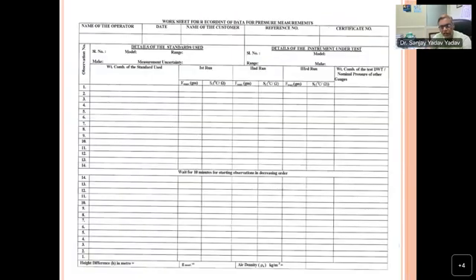This is the data sheet you must use in your calibration procedure, because sometimes when you perform the calibration, the calculation is done a little bit later, so you can have all the information at the time of calibration, what the room temperature was at the time of measurement. So you will avoid all the blunder in your measurement when you are using such a data sheet in your measurement. These points are in increasing order, then wait for 10 minutes, and then you can start in decreasing order. So when you are taking measurement in decreasing order, if anything is written by the operator in here in increasing order, that blunder will not repeat here. So we have avoided blunder in this data sheet itself.